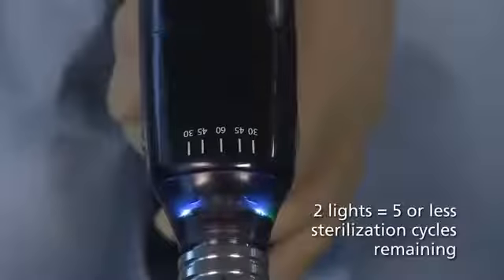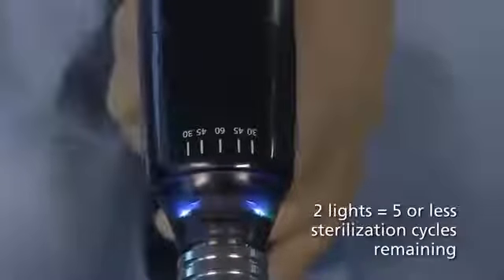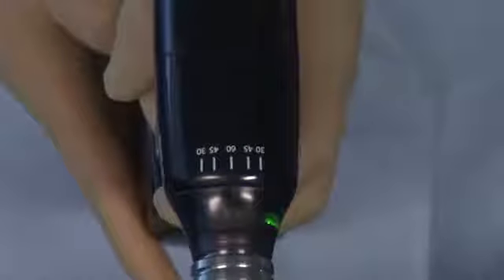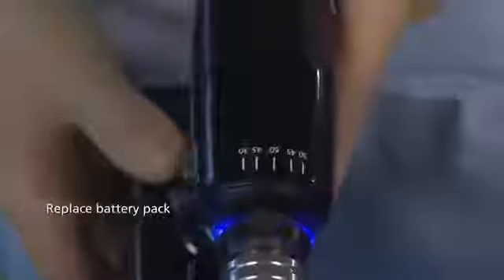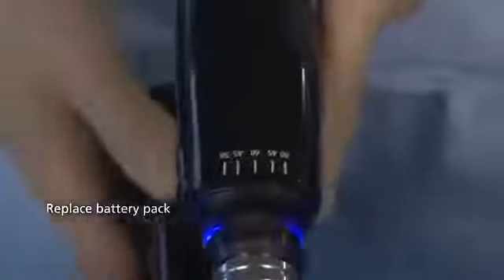If 2 white lights appear, then there are 5 or less procedures left on the handle before end of life will be reached. In this situation, press and hold both the open and close fire buttons simultaneously. The white firing progress indicator lights will flash once for each remaining sterilization cycle. This sequence will continue as long as both buttons are held. If the battery pack needs to be replaced, the general status indicator lights will show a solid blue color. No other light will be illuminated in this situation.